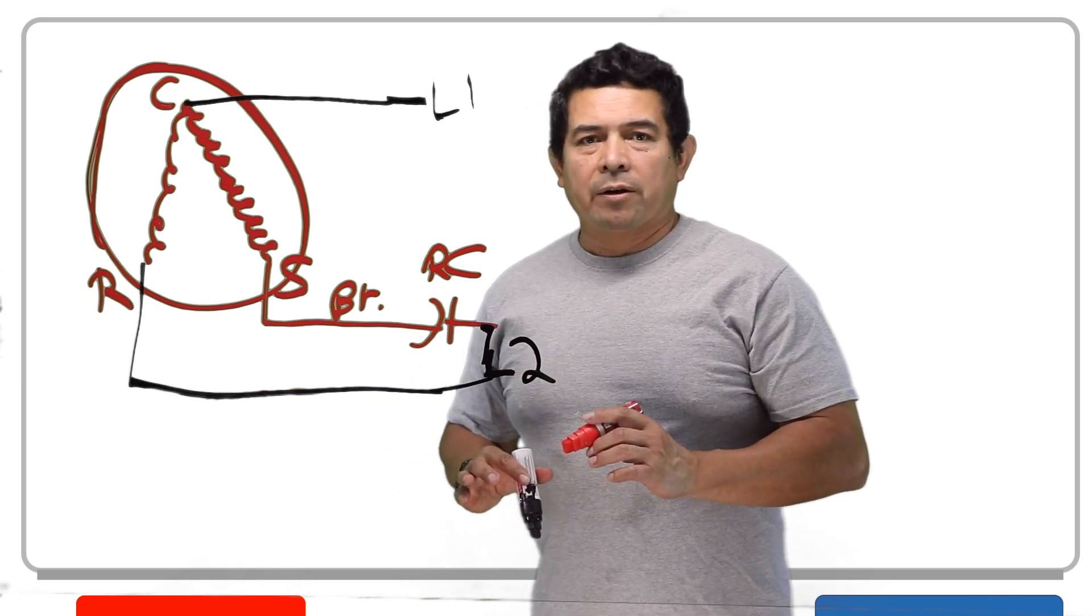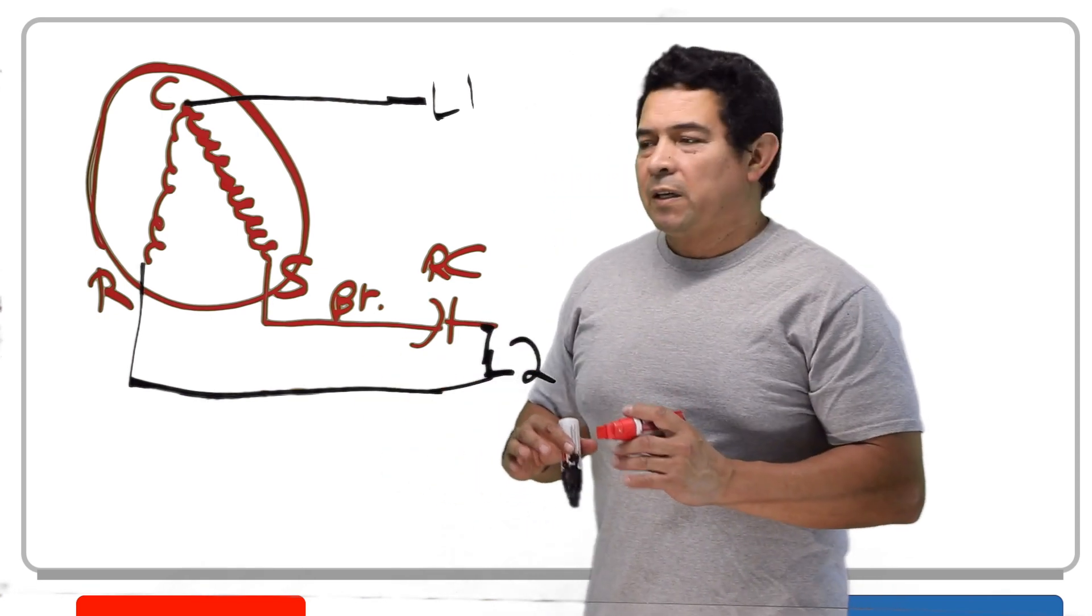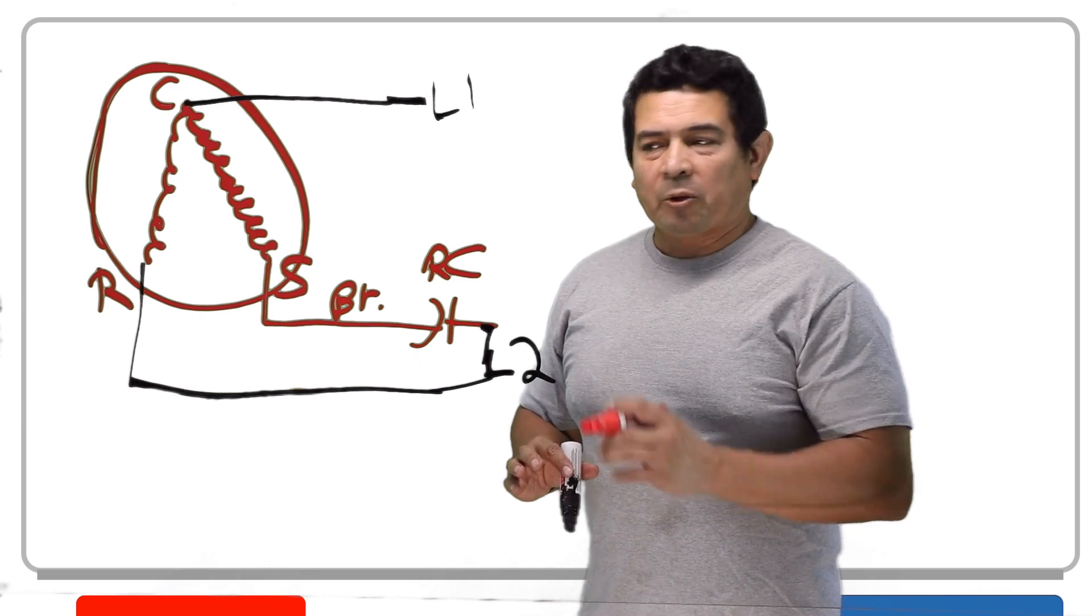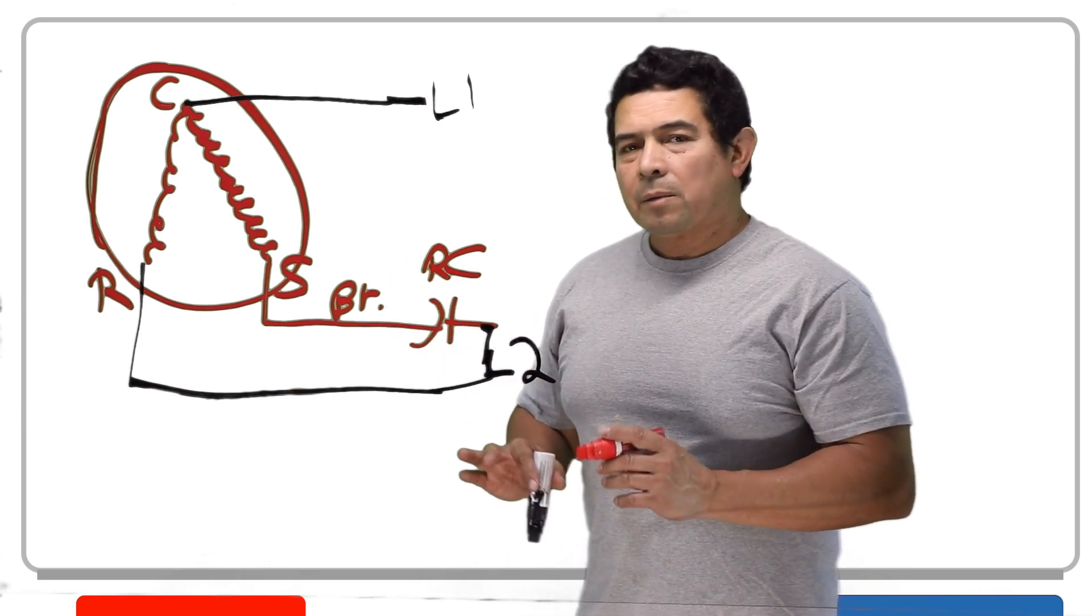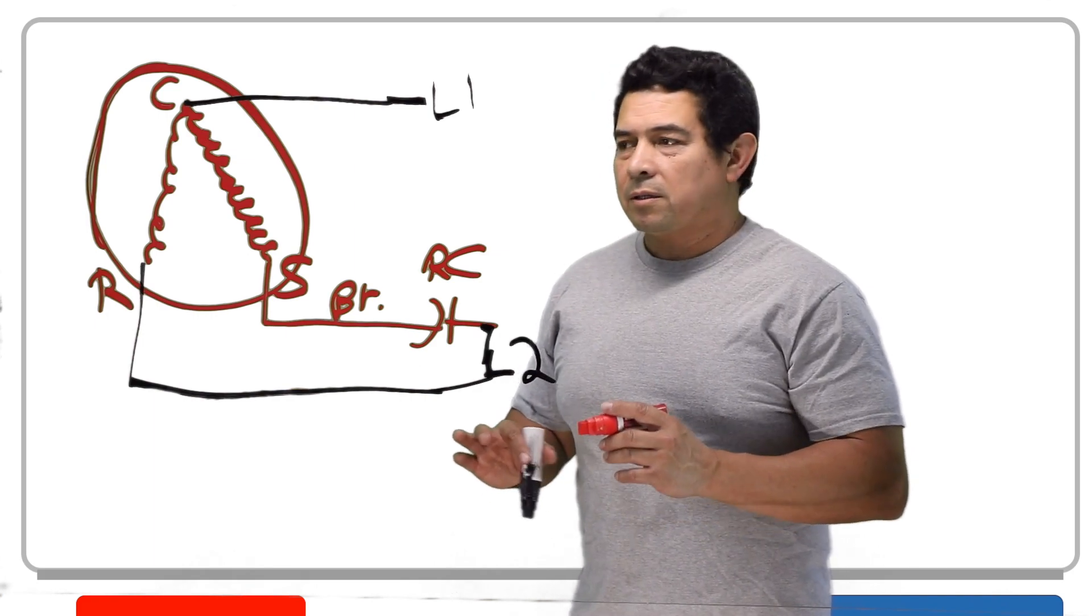One thing I was saying that you should remember is the same line that feeds the run winding feeds the capacitor, and the capacitor always feeds my start winding. This is how they always go wired. If you wire it up another way, it's just going to mess things up. But now, since we know how this goes wired, let's talk about what it does.